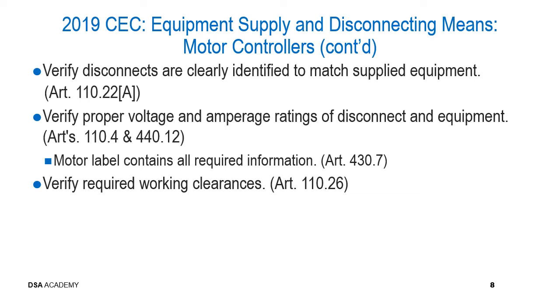Additionally, the motor label contains all the required information that you're going to want to review. So when you are reviewing to make sure that the disconnect matches the motor, be sure and take a picture of the motor with all the parameters identified on it and take that down to where the disconnect is to make sure the parameters match. This is reiterated in Article 430.7. And almost most importantly, verify that the required working clearances are established and maintained for both the motor or the motor controller and the associated panel feeding the motor. And again, this comes from Article 110.26.